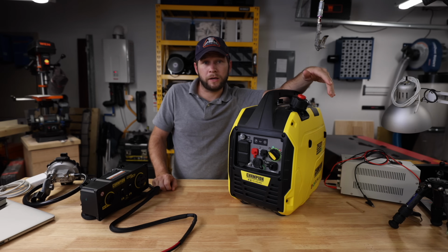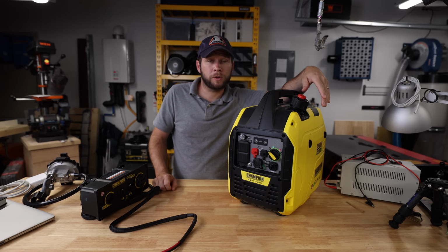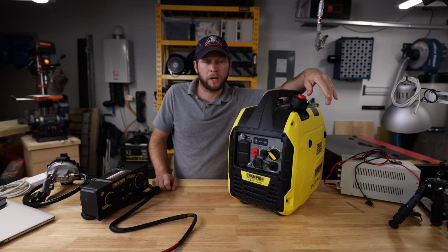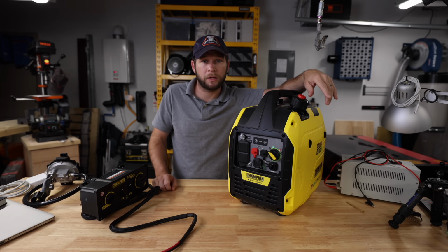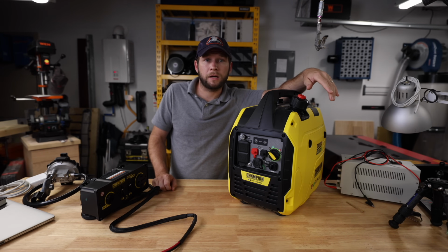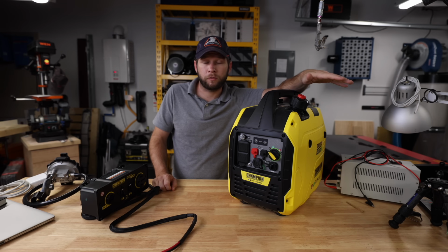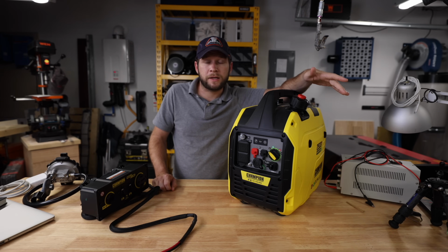The portable generators are inherently dirty power. A lot of these have a range of about 25% total harmonic distortion. This is kind of the variation that they can have in their power quality. This is an issue because with most electrical grids, so most large power plants, standard thing, you'd have an electric meter and plug into the wall. They're really designed for 3%. That's kind of the range that they try to keep, is 3% power variation.